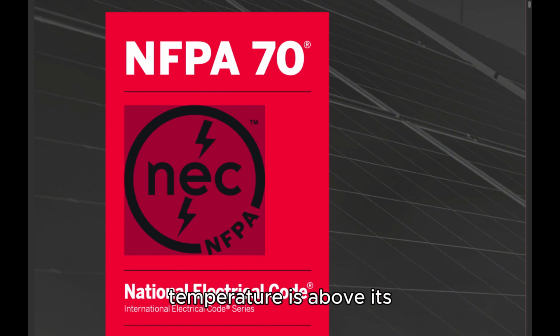is above its flash point, or a Class II combustible liquid that has a vapor pressure not exceeding 276 kPa (40 psi) at 38C (100F), and whose temperature is above its flash point. CMP14 voltage of a circuit. The greatest root mean square (RMS) effective difference of potential between any two conductors of the circuit concerned.